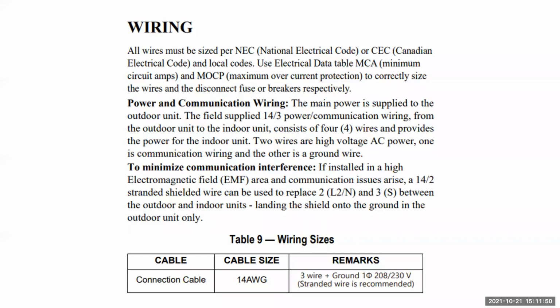So this is straight out of the installation manual. Always use stranded shielded 14-3 gauge wire. This also includes the temporary wiring that I just mentioned, when you just wire between point A and point B and throw it out the window.